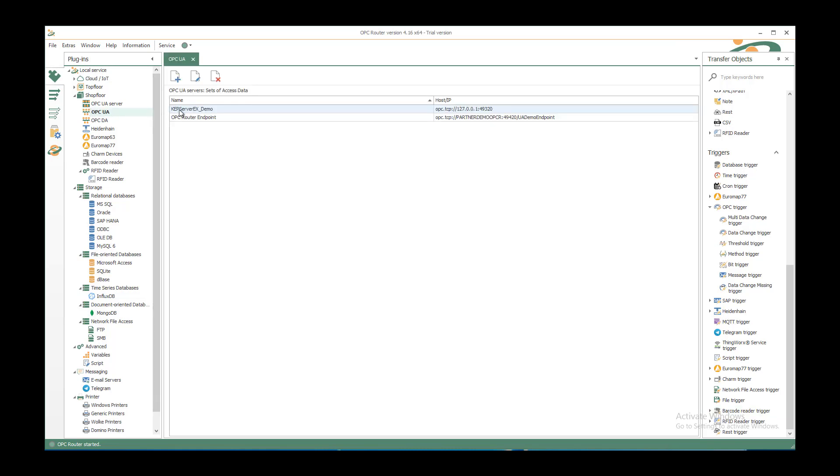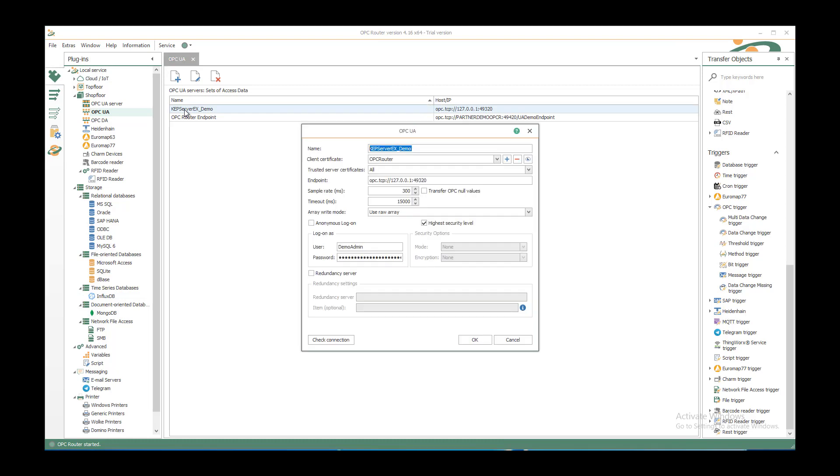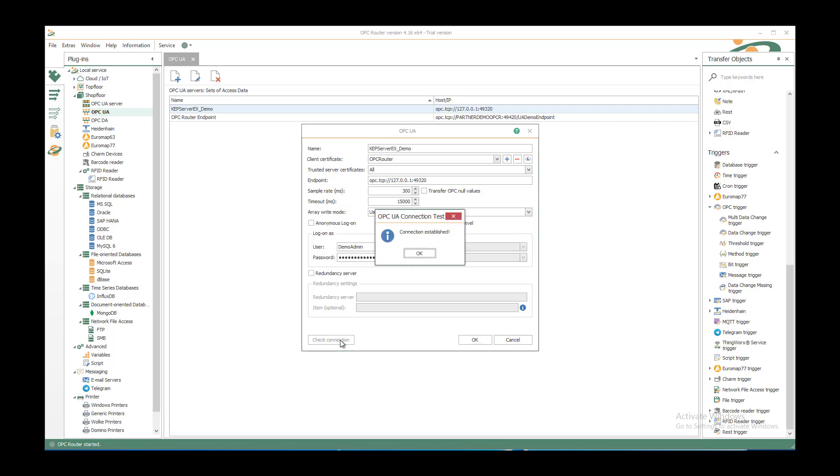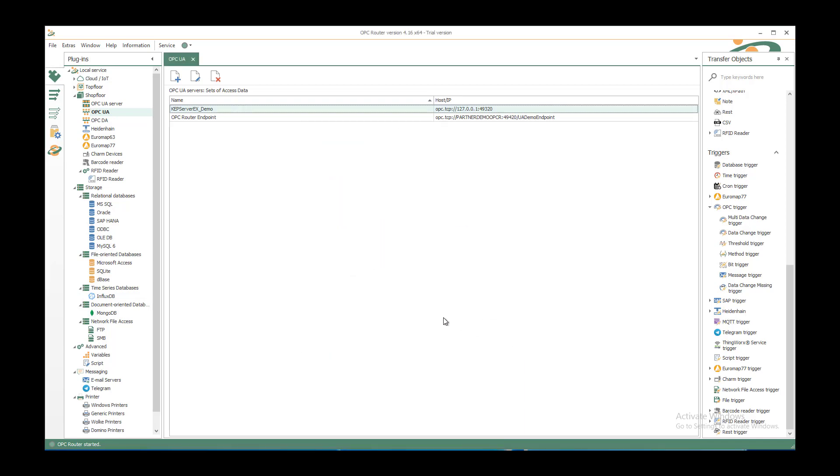You can select the predefined OPC UA server or create a new one. I'll show you my configuration. I have created a client certificate with the plus button and selected an endpoint, logged on as a specific user with the highest security level available at the target OPC UA server. I can check the connection to make sure it's established. It's OK. If you want to save the changes, you can use the OK button.